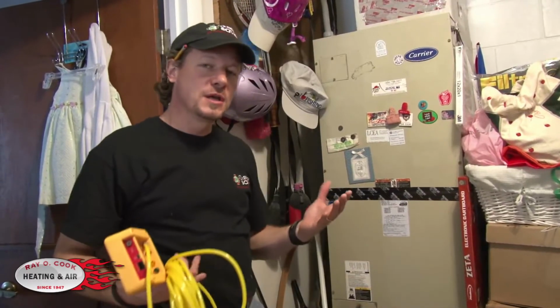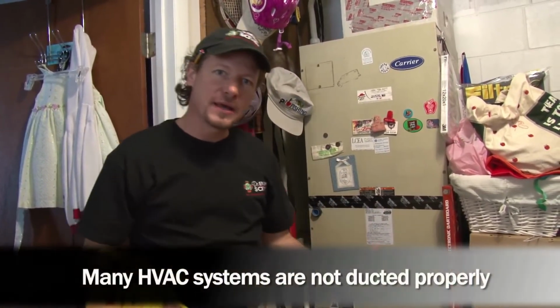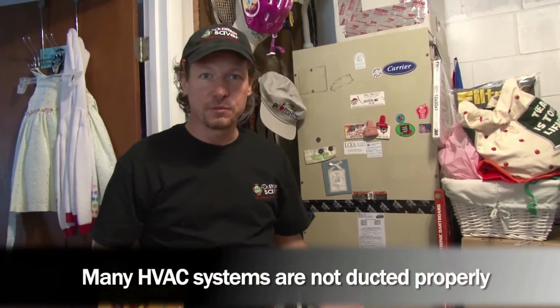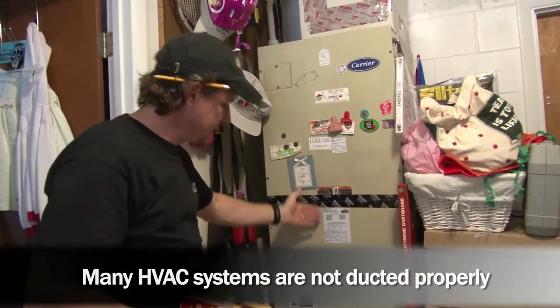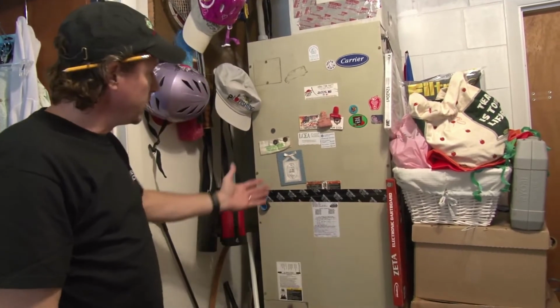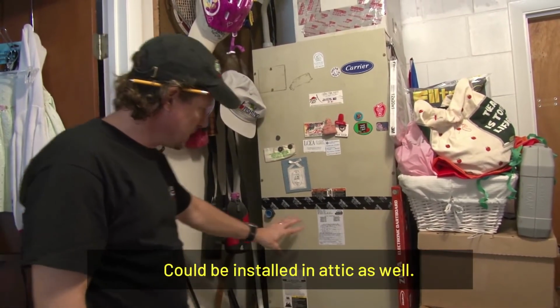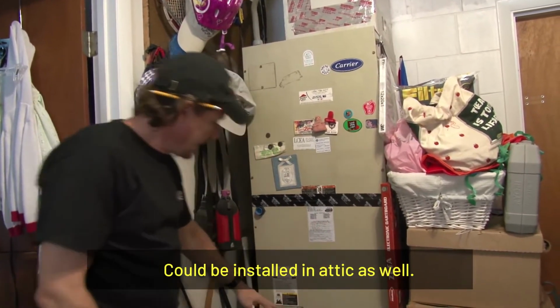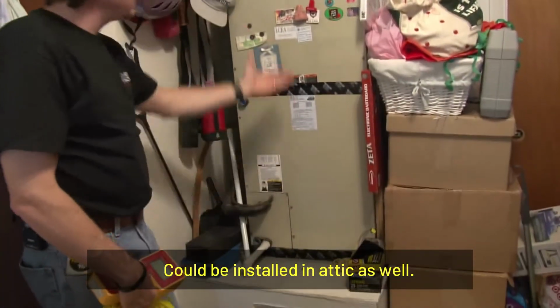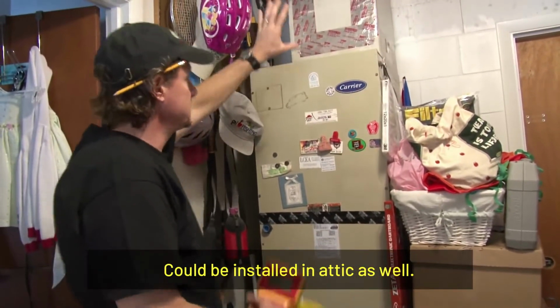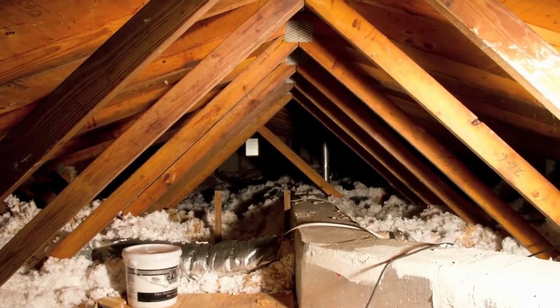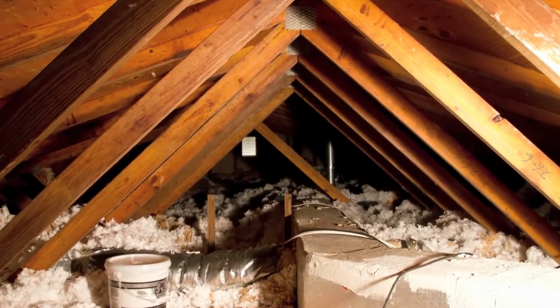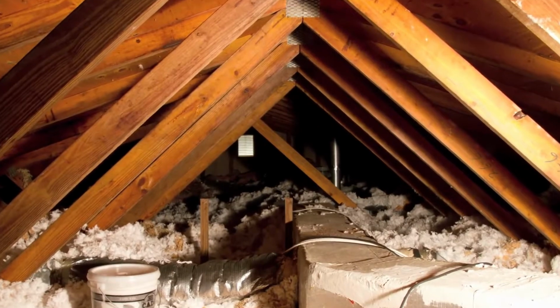One of the big problems with heating and air conditioning systems in any climate is that they're not pressure balanced throughout the house, with an even distribution of supply air to each room and return air from each room. In this case, this is very common around here. We have our air handler, so this is our air conditioning, and we have our return coming in the bottom and our supply duct going out the top. Now the supply trunk line runs through the attic and supplies are branched off to each room.